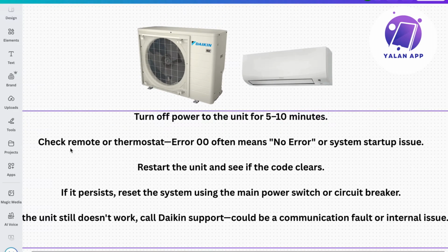So then you're going to check the remote or thermostat. Error 00 often means no error, just so you know, or system startup issue. Sometimes, by the way, after you get this 00 error, you will sometimes get another error code that might clarify even more exactly what the issue is. Not always, but it can happen, just so you know.